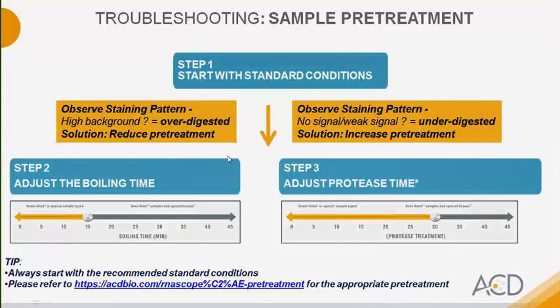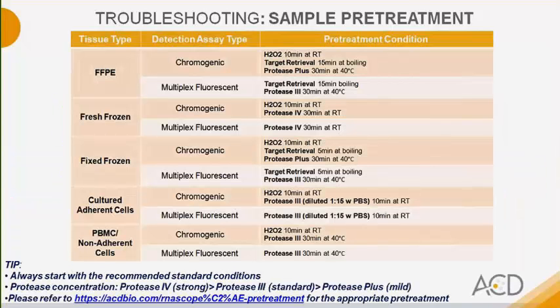For example, if you are observing high background, that means your sample may have been over-digested. So the solution is to reduce the pretreatment condition by dialing the protease down from 30 minutes to 15 minutes. And if you have observed no signal, that means your sample has been under-digested, so the action to take is to increase the pretreatment by increasing the boiling time from 15 minutes to 30 minutes. So once again, please refer to this website for recommended standard pretreatment conditions.